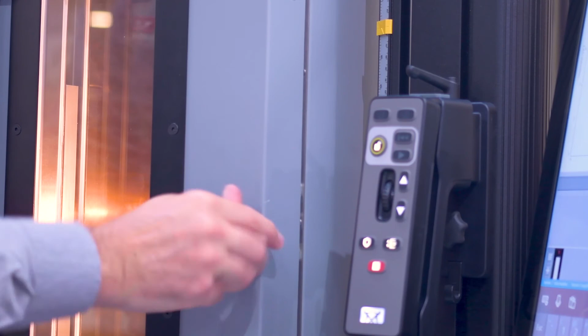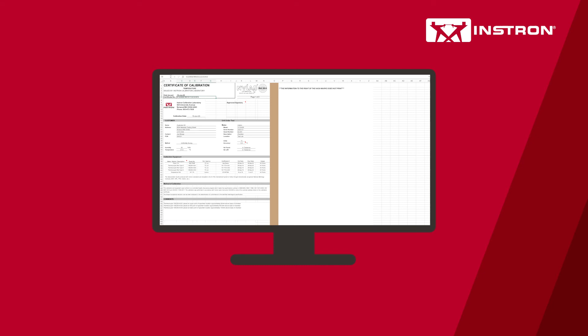All calibration services that we deliver are accredited by NVLAP, an ILAC MRA signatory, under lab code 200301-0. After the calibration has been completed, you will receive a Calibration Certificate, which includes all of the critical evidence that your system is performing at your defined levels.